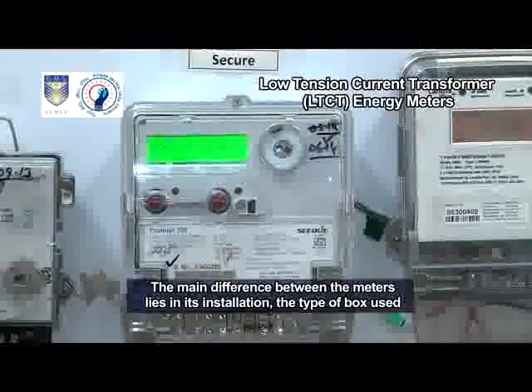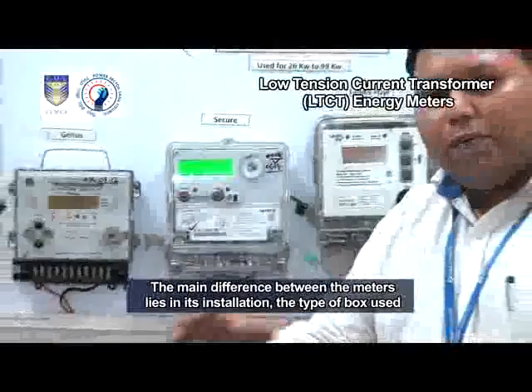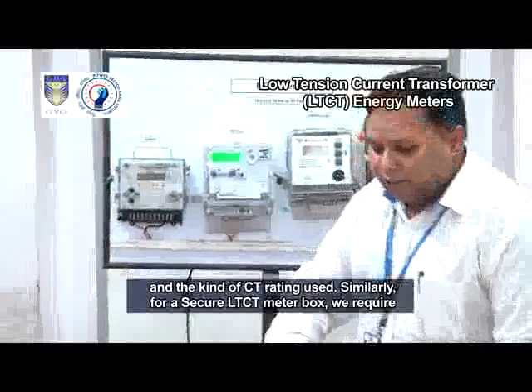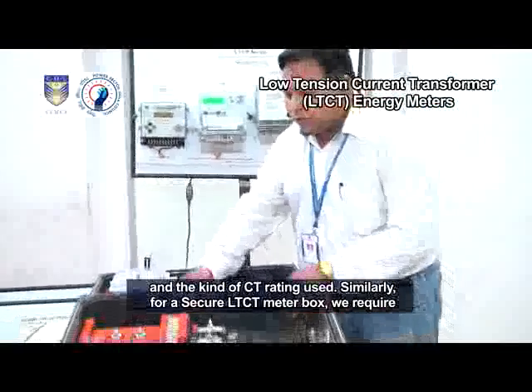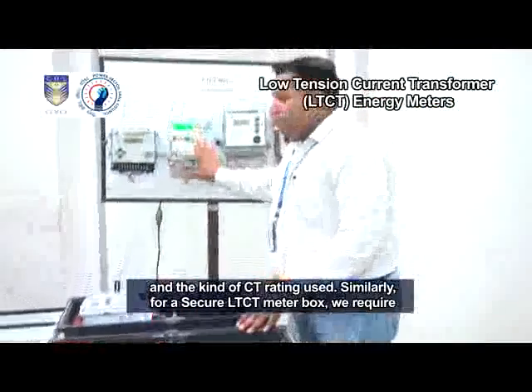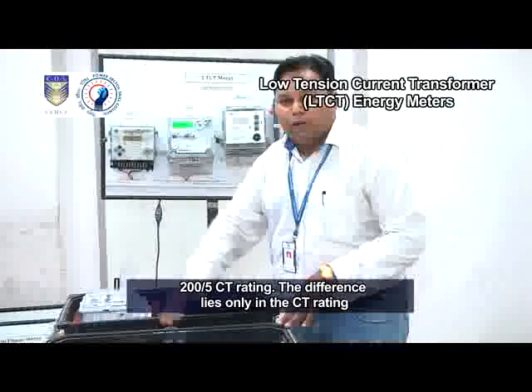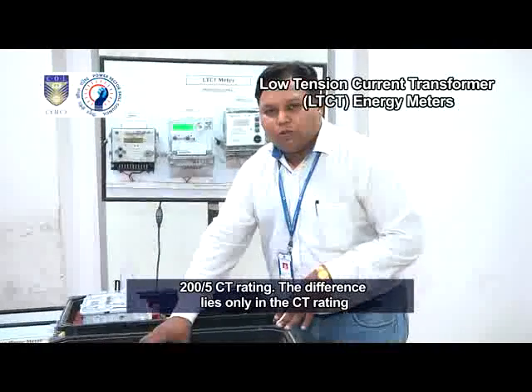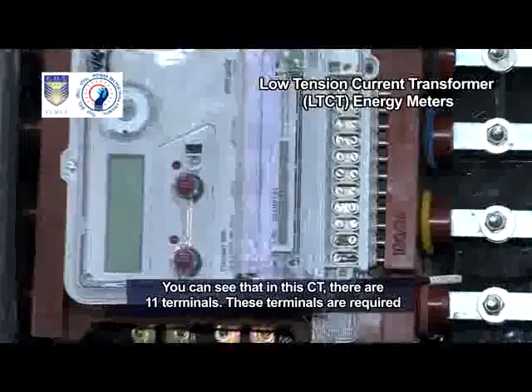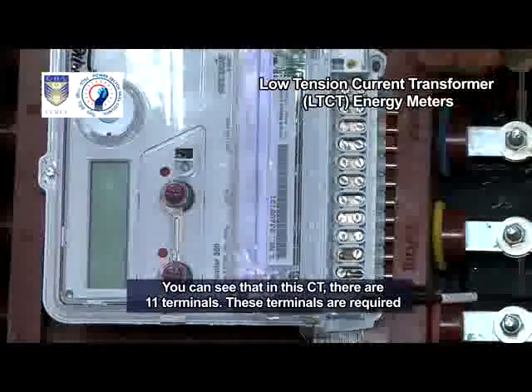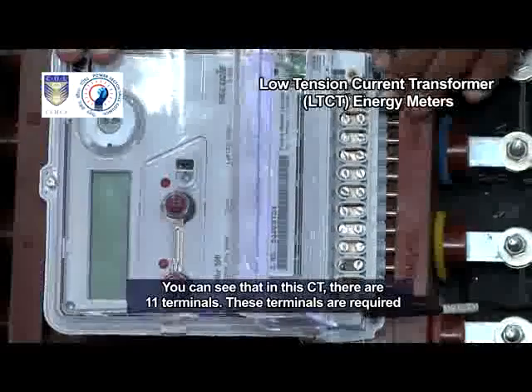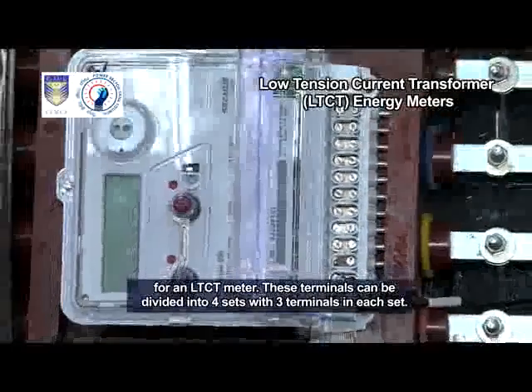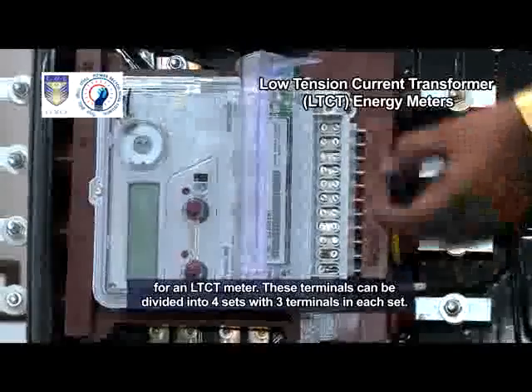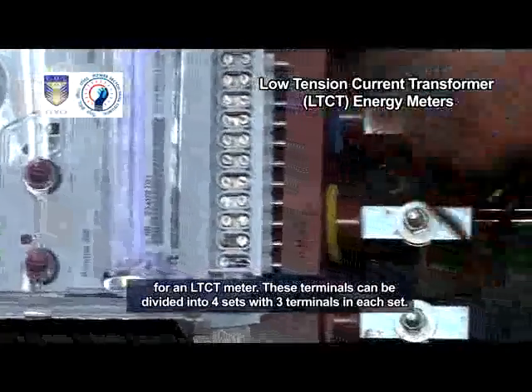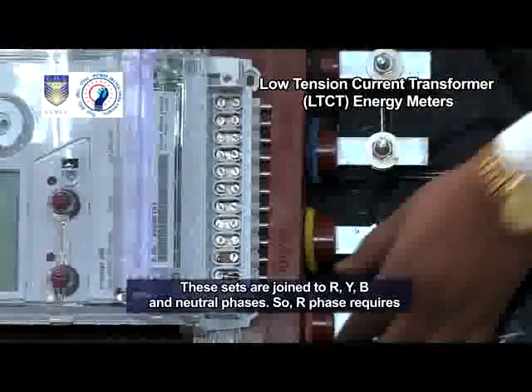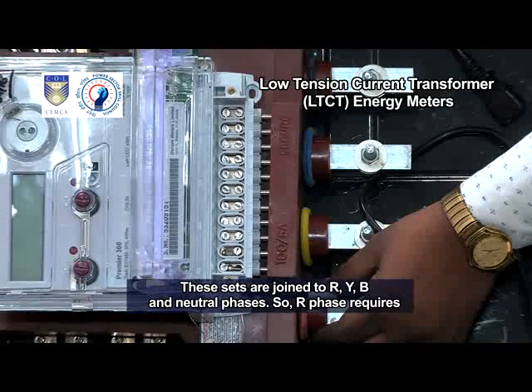The main difference between the meters lies in its installation, the type of box used, and the kind of CT rating used. Similarly, for a Secure LT-CT meter box, we require 200 by 5 CT rating. The difference lies only in the CT rating. You can see that in this CT, there are 11 terminals. These terminals are required for an LT-CT meter. These terminals can be divided into 4 sets with 3 terminals in each set. These sets are joined to R, Y, B and neutral phases.